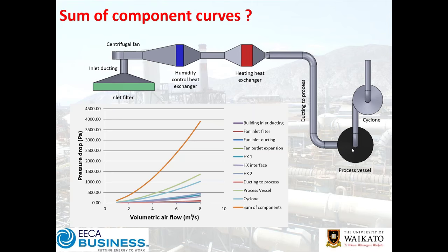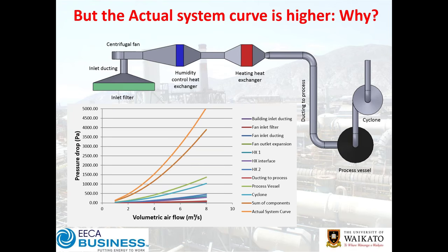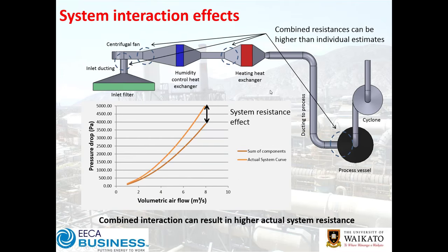You get your total system curve as a sum of those individual components. What's interesting is that the actual measured system curve is quite a bit higher — our cumulative sum of all components sits just under 4,000 pascals, but in reality as a system it's closer to 5,000. So the question we want to ask is: why is this system pressure drop so much higher for the same flow?